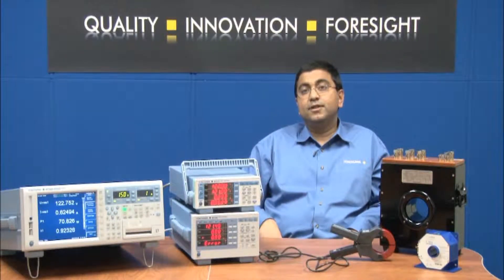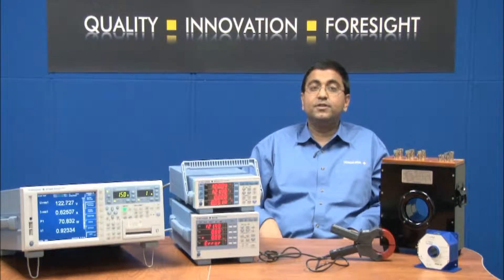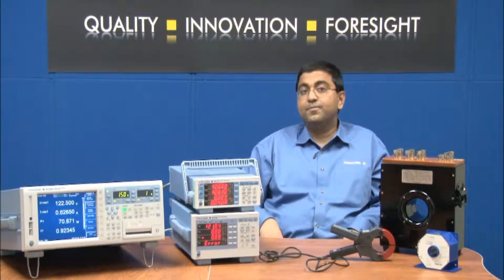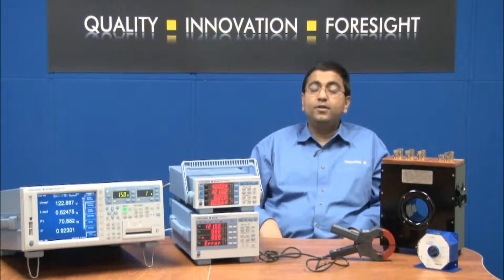In summary, for Yokogawa power analyzers, when measuring large currents, wire the circuit such that the voltage measurement circuit is connected to the load side. And when measuring small currents, wire the voltage measurement circuit to the source side.